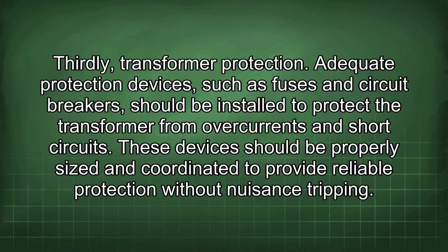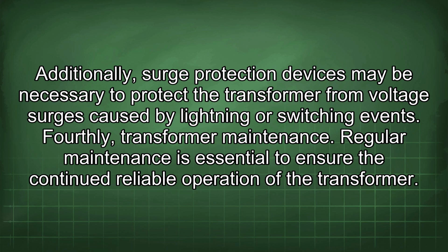Thirdly, transformer protection. Adequate protection devices, such as fuses and circuit breakers, should be installed to protect the transformer from overcurrents and short circuits. These devices should be properly sized and coordinated to provide reliable protection without nuisance tripping. Additionally, surge protection devices may be necessary to protect the transformer from voltage surges caused by lightning or switching events.